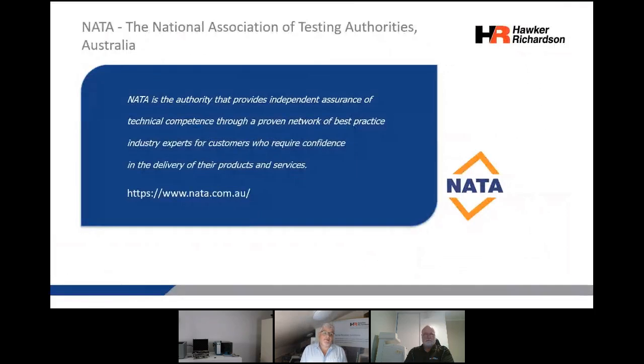The equipment used to calibrate and check your screw feeder or any torque control tools needs to be tested against a known standard. Our torque testing equipment has been calibrated in NATA certified laboratories and carries a current certificate of calibration. Therefore, the torque tools calibrated by Hawker Richardson are traceable to a NATA certified instrument.